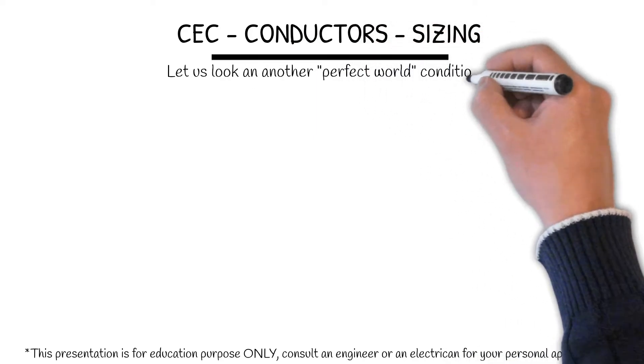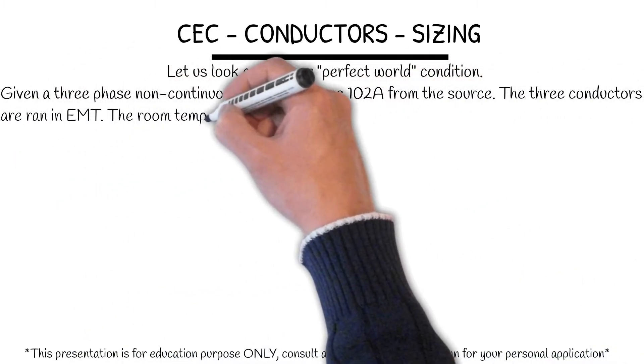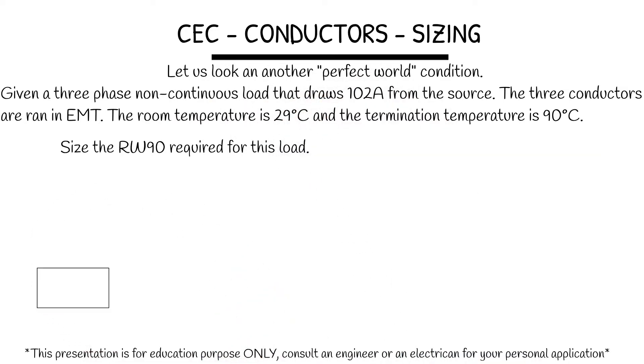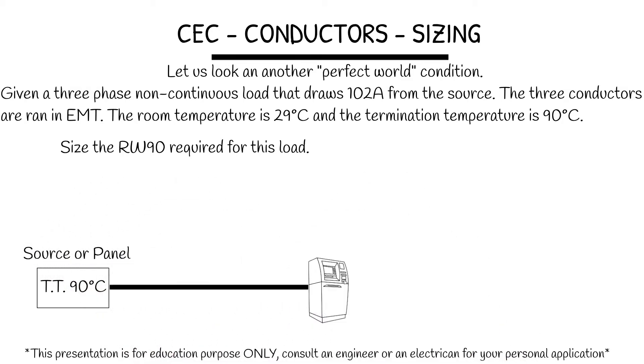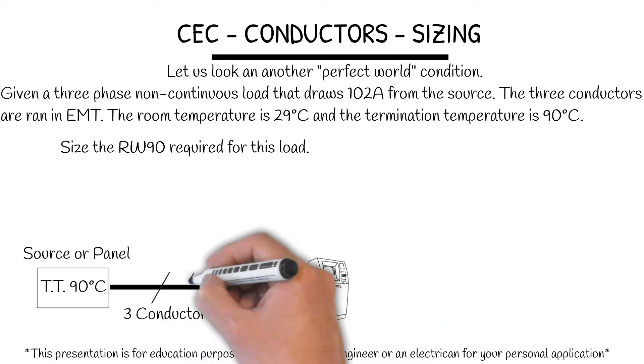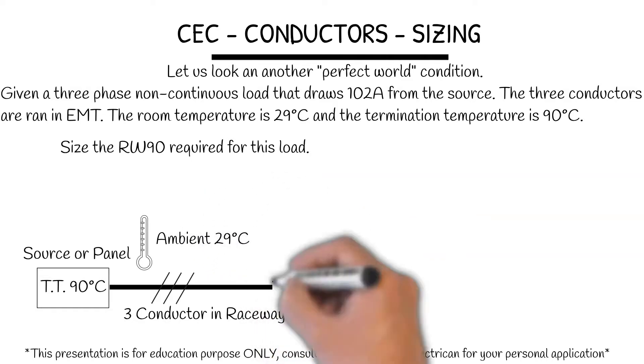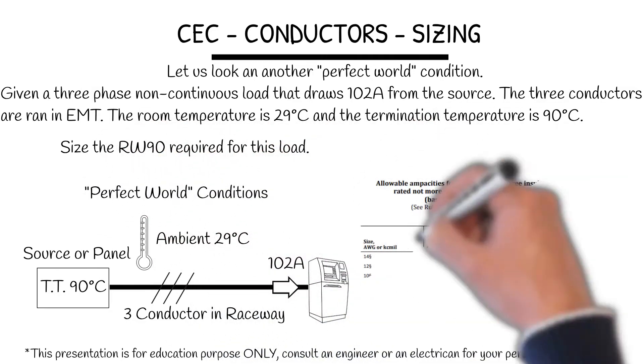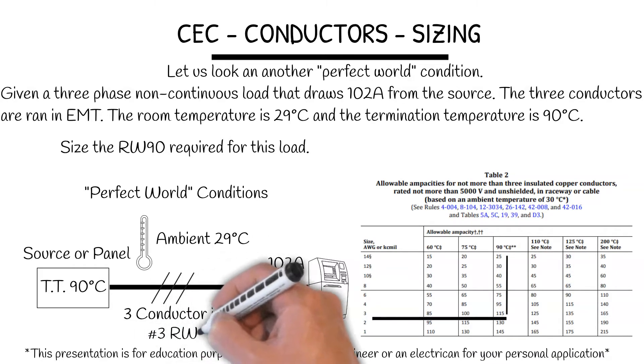Let us look at another perfect world condition. We're given a three phase non-continuous load that draws 102 amps from the source. The three conductors are RW90 in EMT, and the room temperature is 29 degrees Celsius, and the termination temperature is 90 degrees Celsius. Size the RW90 required for this load. This is the perfect world condition. Now let's recall Table 2. I can go down the 90 degree column. Where 102 amps fits will be 115 amp capacity for a number 3 size wire.